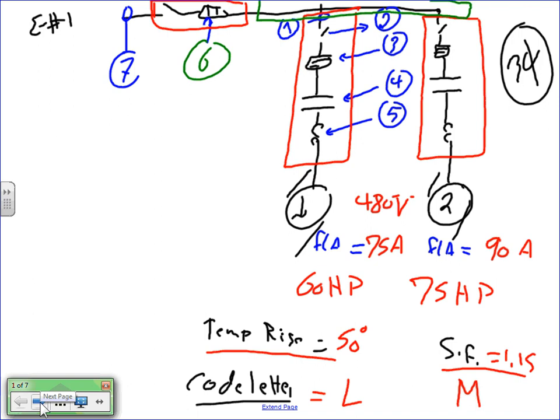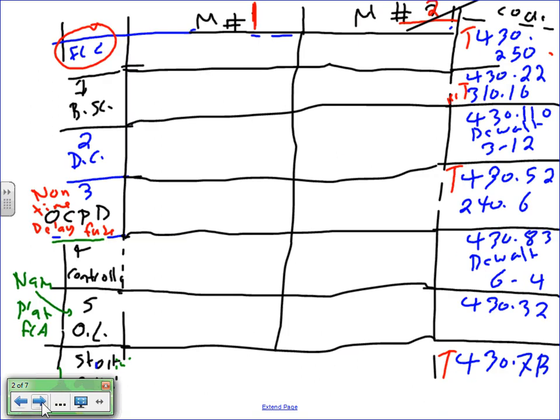Now, Tom, my friend, you were showing me the other day the standard that you guys have where you work and how the size of the overcurrent protection device is set. I want you guys to pay a lot of attention to the size of the overcurrent protection device versus the size of the conductor for motors. Because you go to a lot of companies that have their own standards and they size the cables based on the overcurrent protection device. It's great if you're doing panels, awesome, that's the best way to do it. If you're doing motors, you almost always end up oversizing the conductor. If that's your company's work, no problem. That's the standard that they use. Otherwise, you might be able to save some copper as a contractor if you do the following.